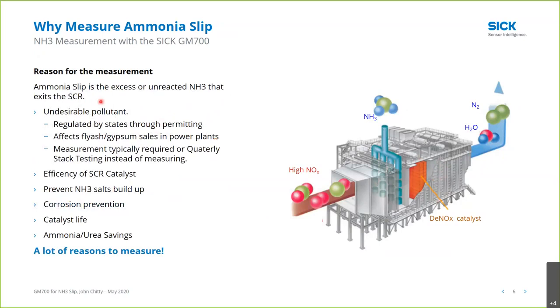The reason for the measurement: ammonia slip is the excess or unreacted ammonia that exits the SCR. This is an undesirable pollutant. It's regulated by some states through permitting. I think by most states. In power plants, it affects the fly ash, which is sold as gypsum. Based on your permit, you may have to do quarterly checks or stack testing and/or measuring. It depends on the state that you're in. Ammonia slip affects the efficiency of the catalyst and the life of the catalyst. Too much of it can cause ammonia salts buildup, which can cause corrosion. And ammonia is expensive, so if you're putting too much in, it costs money. So there's a lot of good reasons to measure in addition to EPA regulations.